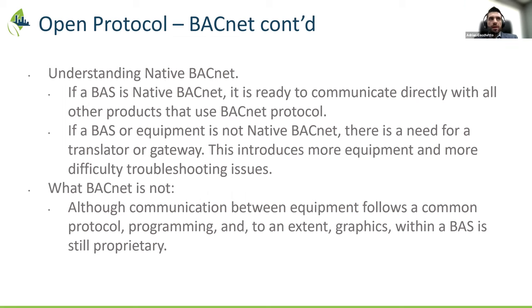When the device is a gateway, I want to stress, like you said, there's nothing wrong with a gateway. Most of the time those gateways are BTL listed themselves, which is a good thing. Where the problems start to happen, I'd say, is more with how that gateway has been set up or programmed, in the sense that the object names are often the issue. We run into scenarios where you discover a controller and the object names are just like AI5, as opposed to something like supply air temperature, which we can understand a lot easier through an English descriptor.